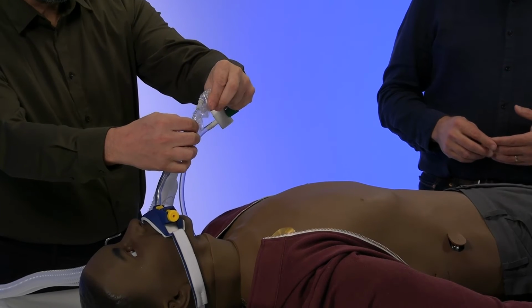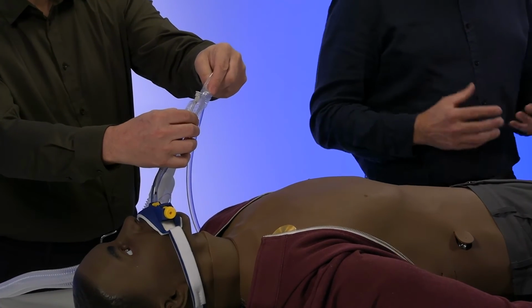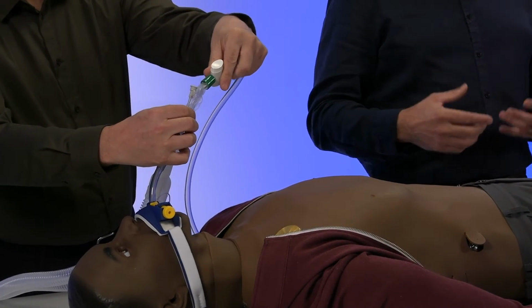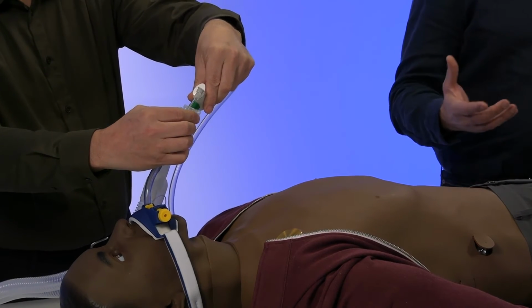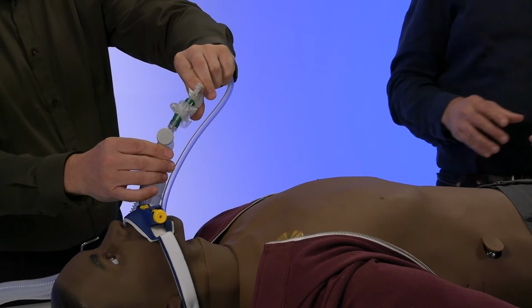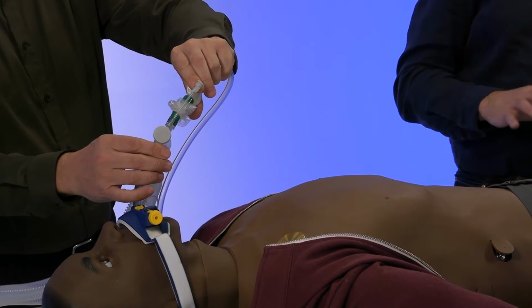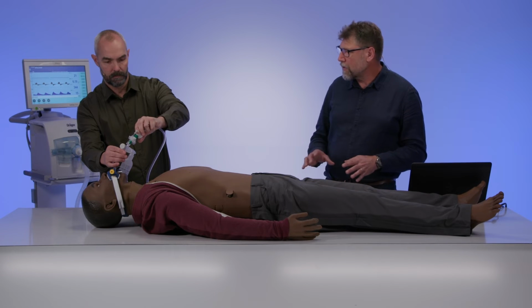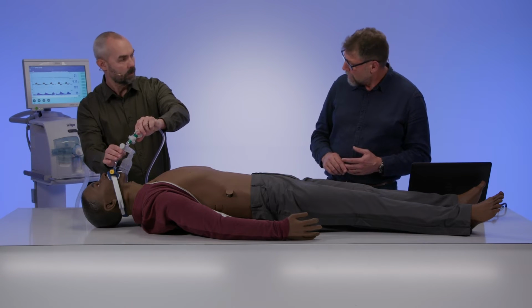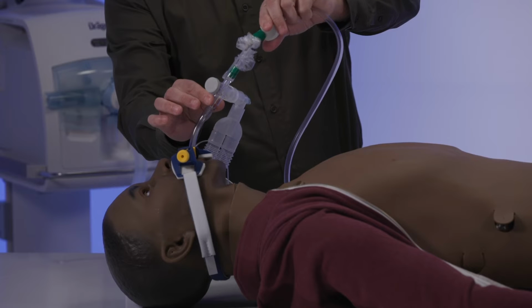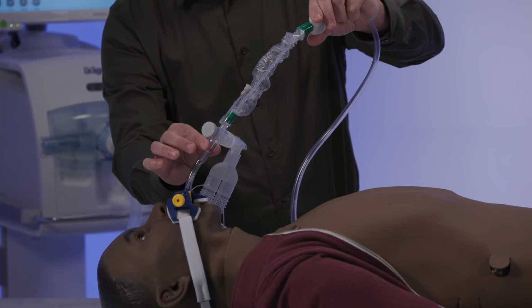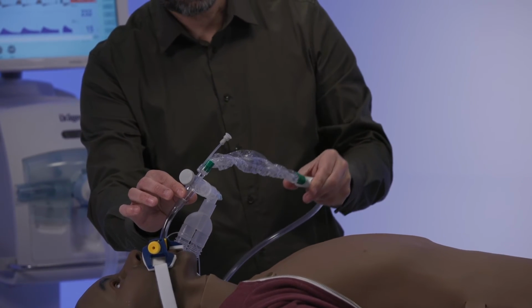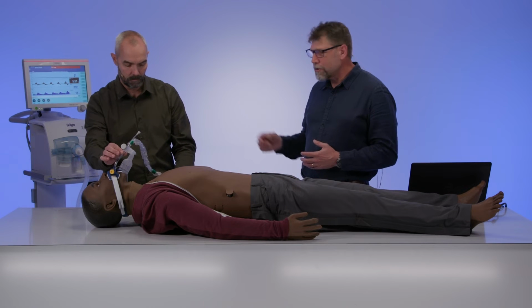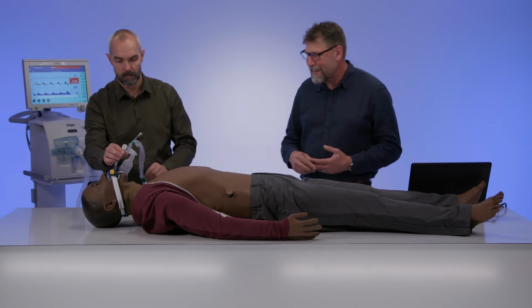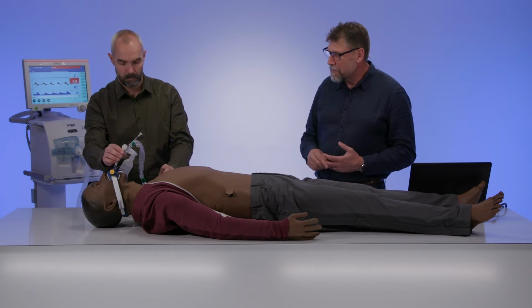I'm inserting the catheter. And of course, one of the things we can do here with the software is simulate things like secretions. We can increase the respiratory rate, which is going to affect the volumes and those sorts of things. So there's a number of things we can do in the software. So doing suctioning. Yeah. Okay, good. And we've just got a low minute volume alarm, and that's because you've sucked some of the air out of the patient.